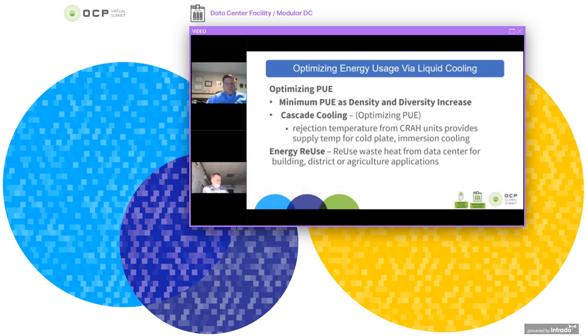The cascade cooling was a topic Tim talked about yesterday, and we're going to talk a bit more about it today. The ability to take the rejection temperature from a computer room air handler or air-cooled unit and use that as the supply temperature for cold plate or immersion cooling, essentially reusing the cooling waste heat over and over again. The concept of energy reuse goes beyond that.